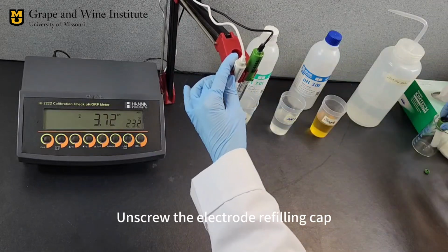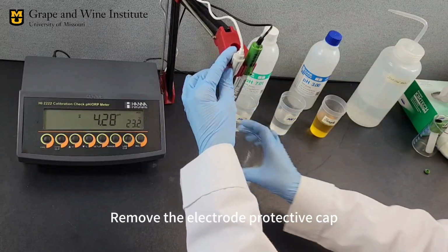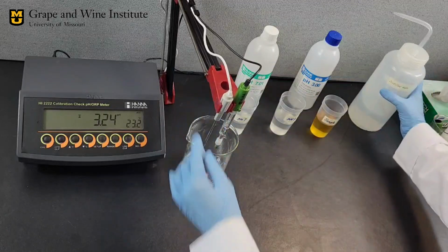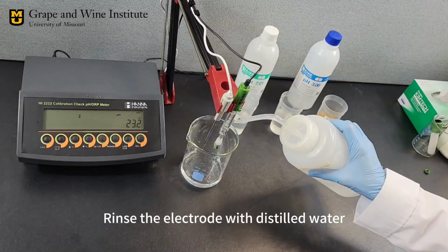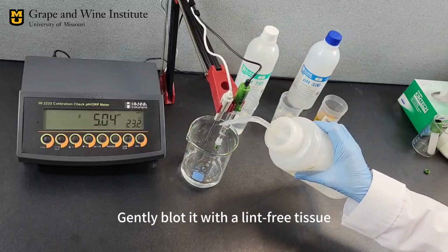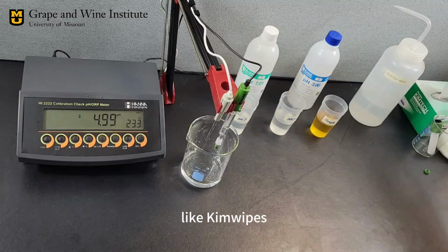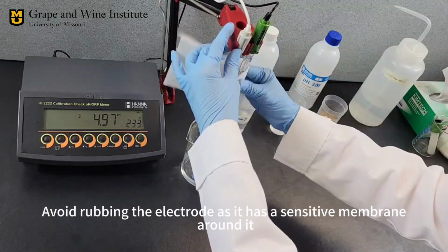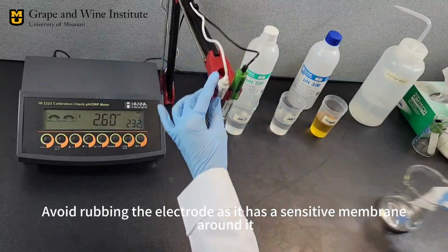Unscrew the electrode refilling cap. Remove the electrode protective cap. Rinse the electrode with distilled water. Gently blot it with a lint-free tissue, like Kimwipes. Avoid rubbing the electrode as it has a sensitive membrane around it.